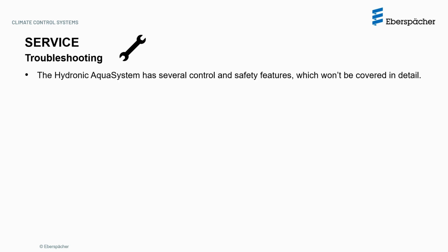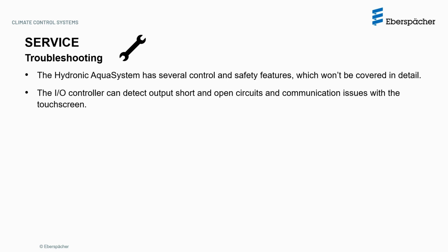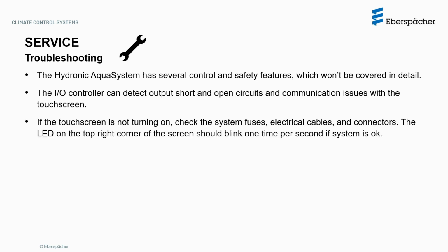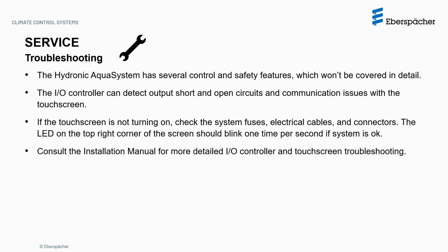Let's talk now about troubleshooting. The Hydronic Aqua System has several control and safety features, which we won't cover in detail here. The I/O controller can, for example, detect output short and open circuits and communication issues with the touchscreen. If the touchscreen is not turning on, check the system fuses, electrical cables, and connectors. The LED on the top right corner of the screen should blink 1 time per second when the system is OK. Consult the installation manual for more detailed I/O controller and touchscreen troubleshooting.